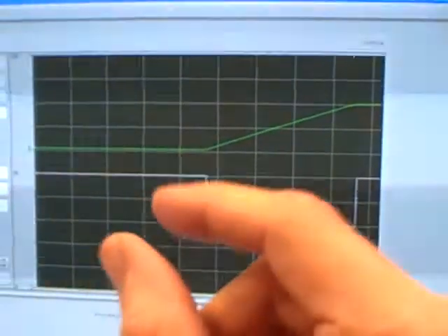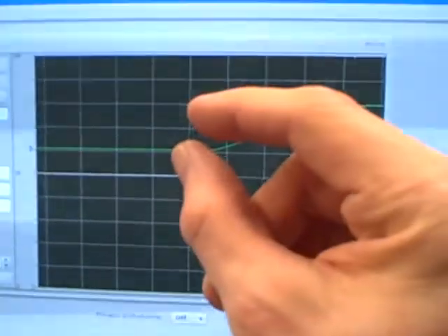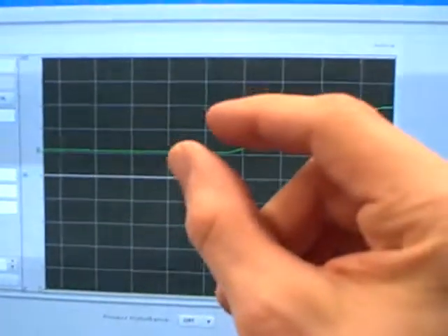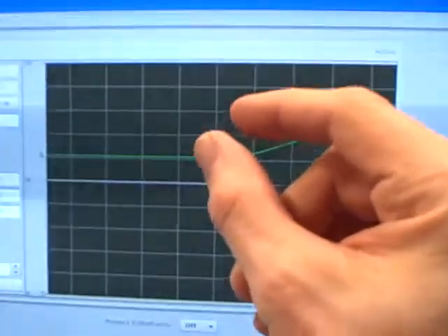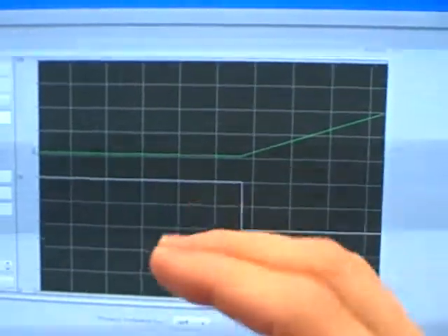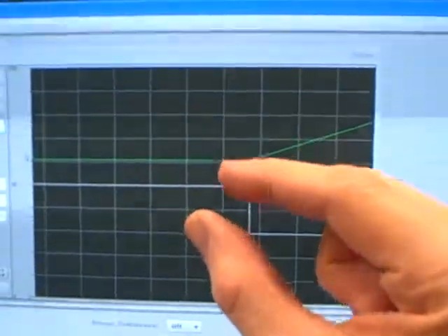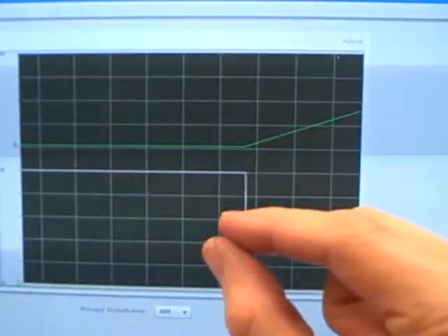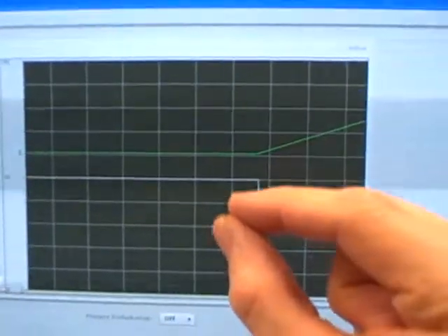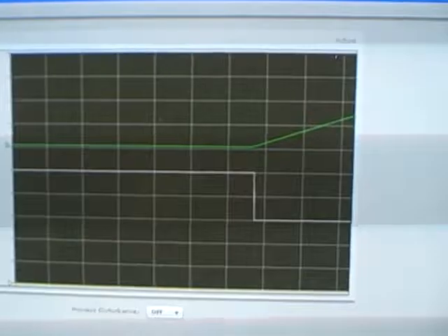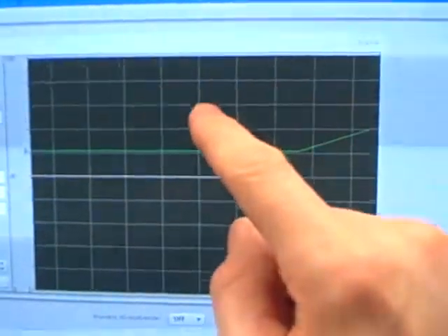All we need to have is proportional action so that when we make a set point change, the valve position will change temporarily, either adding more liquid to or taking liquid away from the tank. As the tank level integrates and approaches the new set point, the valve goes back to its original position, which is precisely what we need in this process to hold the brand new set point value. In other words, we do not need a novel valve position to achieve novel process variable values. Therefore, proportional only control works great.